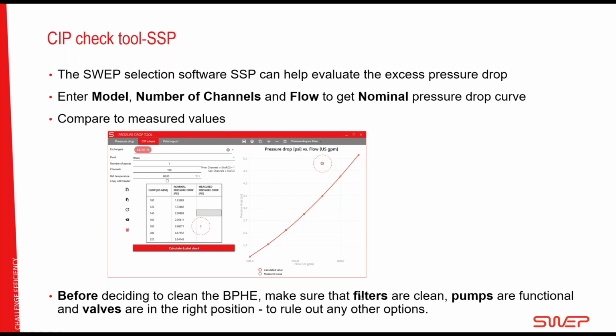Before doing that though, make sure that the filters are clean, the strainers are clean, the pumps are functional, and all valves are open in the right position, to rule out that what you have seen is not due to the fouled up heat exchanger, but because something else is wrong in the system. That will save you time and money sometimes.